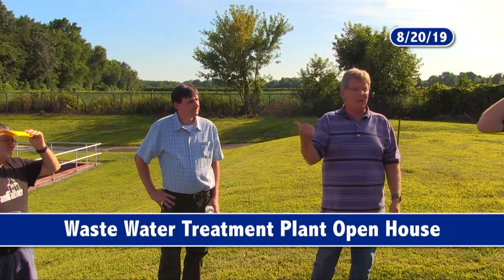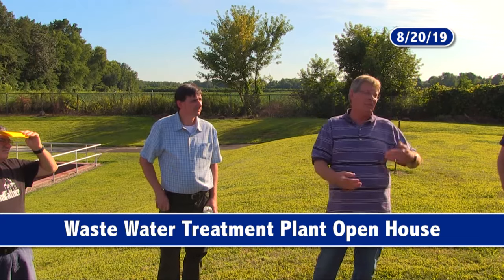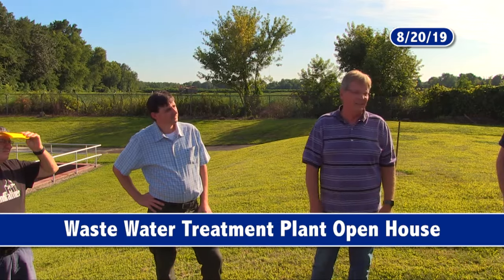In cylinders, yeah. We switched a few years back from 2,000-pound containers to 150-pound cylinders. So there's much less potential for a catastrophic leak. We have to change the cylinders a lot more often. You put one of those 2,000 pound ones on, it was good for like 3 years. But 150 is about every month and a half, we're changing a cylinder. We just changed one yesterday.